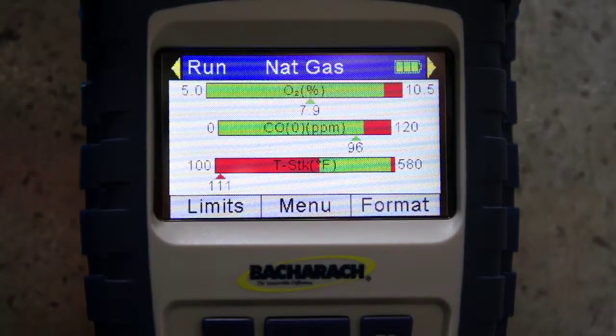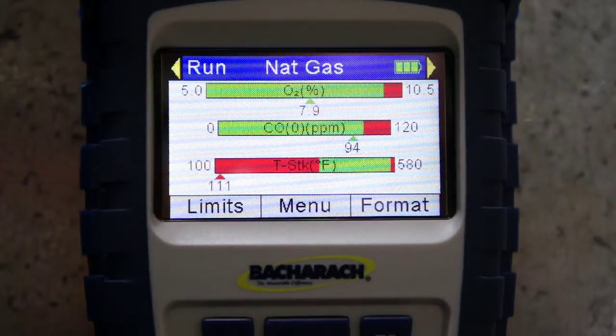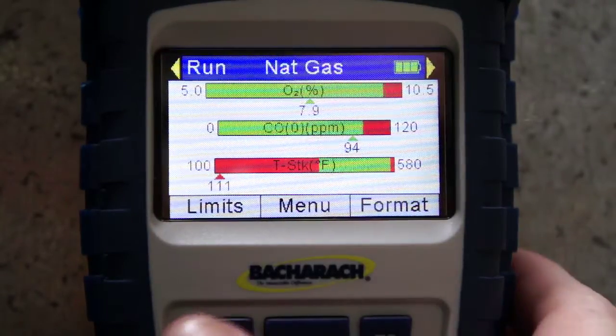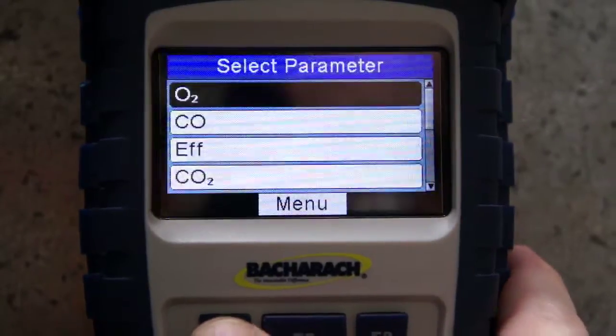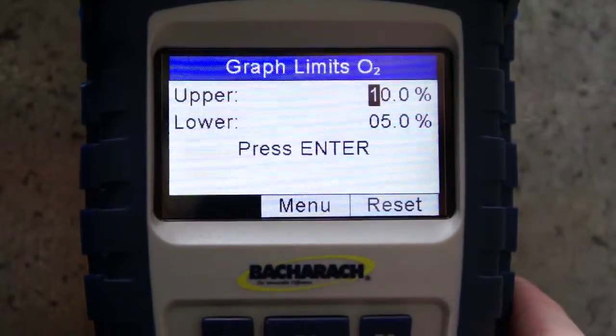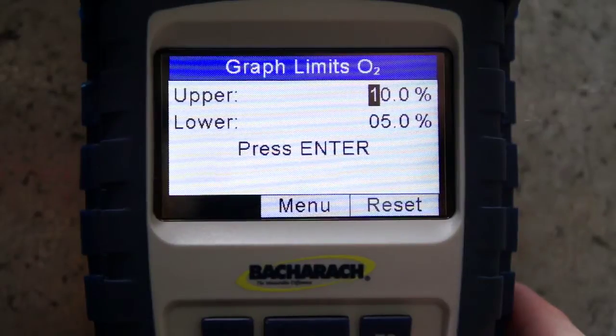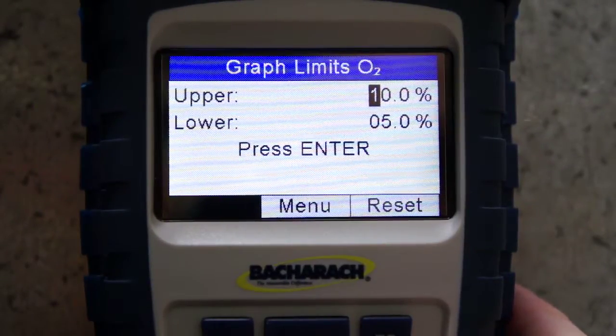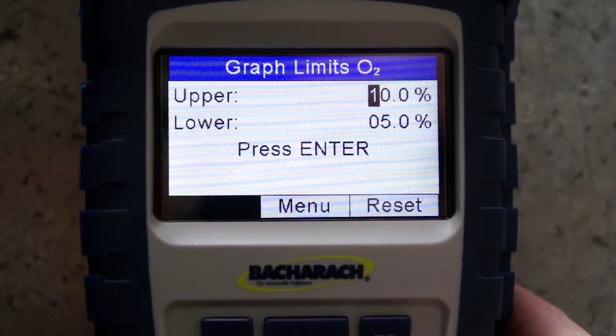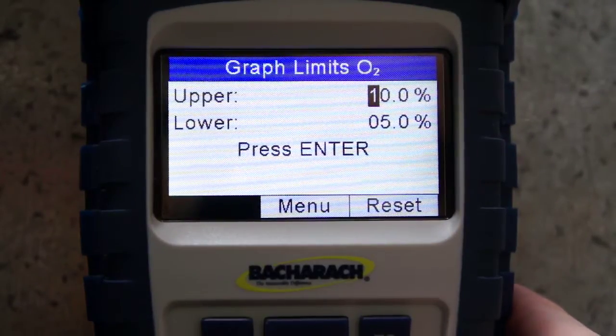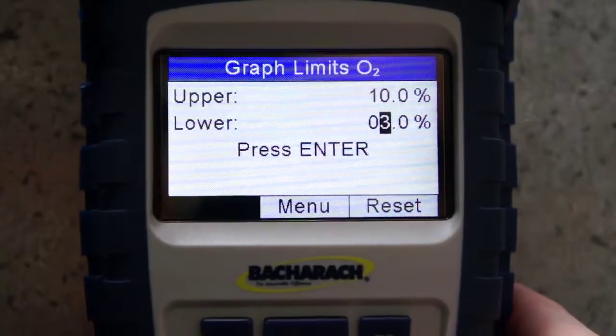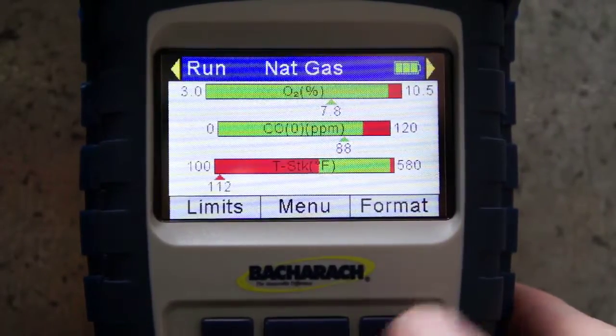So right now I have it set for 5 and 10.5% O2, and that's actually a little bit high on O2, and I'm going to go ahead and change that right now. So I go into the limits, and it pops up O2. And now I want to set my upper limit, which is maybe fine at 10%. That's 100% excess air. But I want to change my lower limit maybe to 3% oxygen. So I'm going to scroll through here, and when I get down to the 5 here, I'm going to drop down 2 to 3, hit enter, and now that stores it.